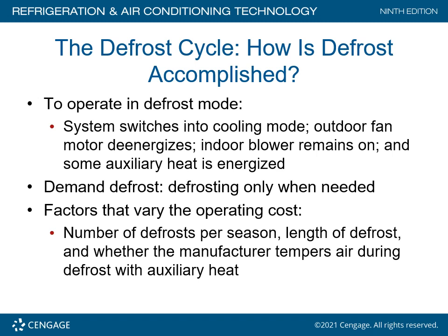Defrost cycle. How's defrost accomplished? To operate in a defrost mode, the system switches back into cooling mode. The outdoor fan motor de-energizes, not the indoor, the outdoor fan motor de-energizes. The indoor blower remains on and some auxiliary heat is energized.